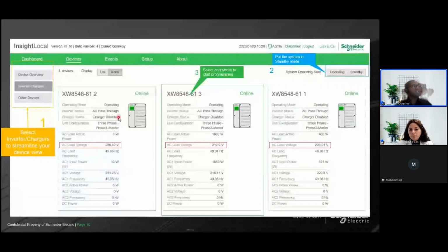So after selecting the inverter chargers, you have to put the system in standby mode. Whenever you're making any change whatsoever to the inverter, make sure it is on standby mode. Click on standby here, and then you can click on any one of these inverters to select and configure that particular unit. It's a step-by-step process, so once you finish with the first one, you go to the second, then the third.